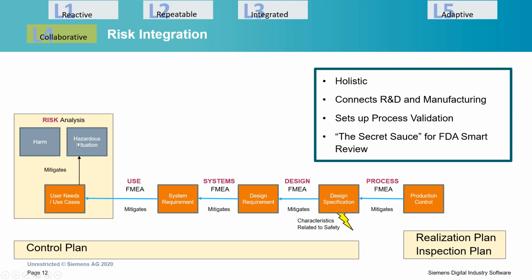And once we do that, we'll have not only the traceability of the design and how to deconstruct the design, how to define what good design is, but also we'll have the context of user harms and or patient harms associated with the construction of the design, the contextualization of the design. And that will, of course, give us our control plan and our inspection plan. That's all part of product realization. So that's our next session.